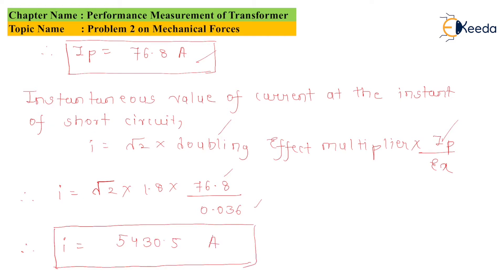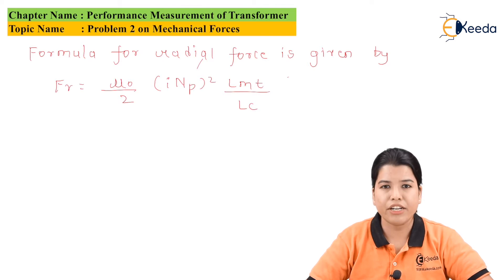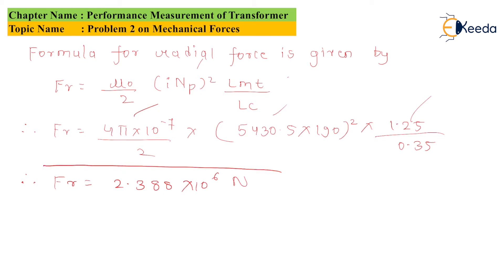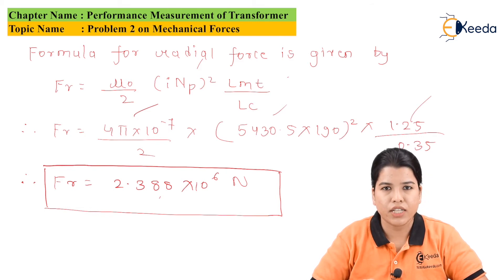Therefore I = 5430.5 Amperes. Now let us find the radial force: Fr = (μ₀ / 2) × (I × Np)² × LMT / Lc. Substituting the values: Fr = (4π × 10⁻⁷ / 2) × (5430.5 × 190)² × 1.25 / 0.35. After solving this equation, Fr = 2.388 × 10⁶ Newton.